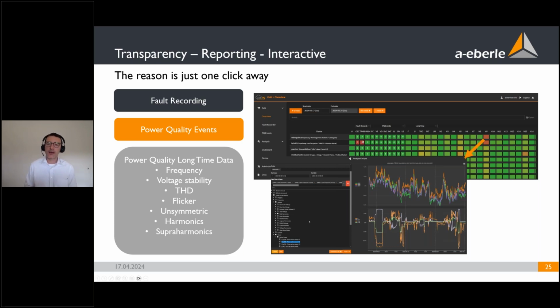Our devices have the opportunity to do fault recording, with 40 kilohertz or true RMS values, which we can measure and store inside the device, even triggered by external binary inputs or outputs. We also have many options for own triggering, like frequency change, load changes, dips, swells, interruptions, and so on. This week, for example, my devices at home recorded different disturbance fault records, and if you click on that, you go deeper into the data.